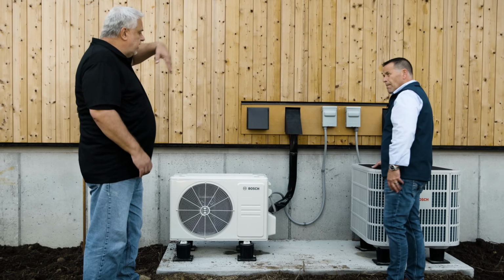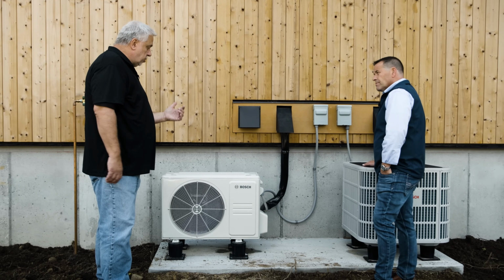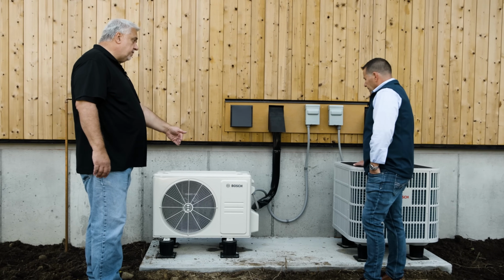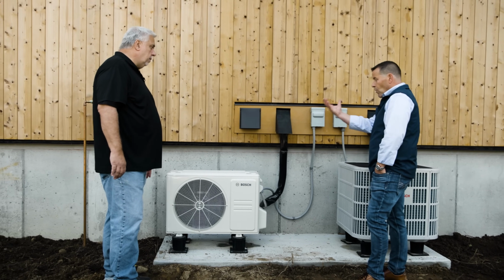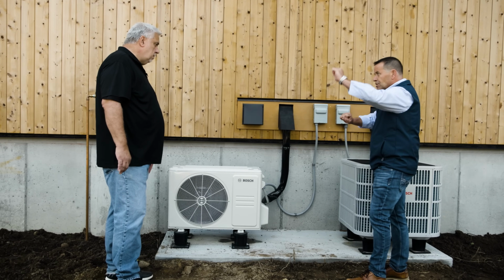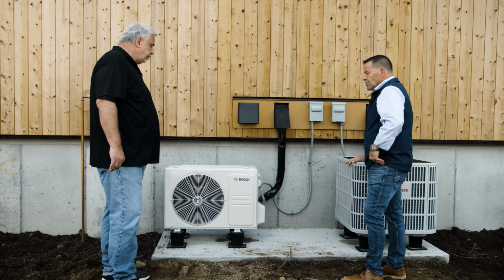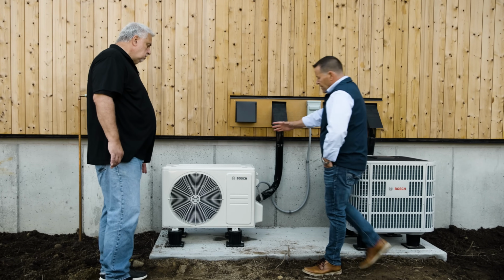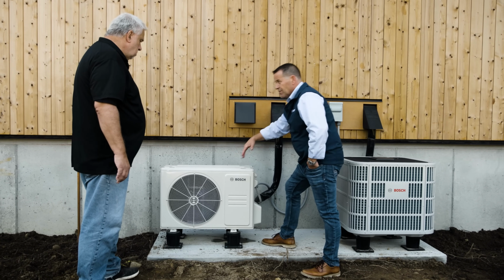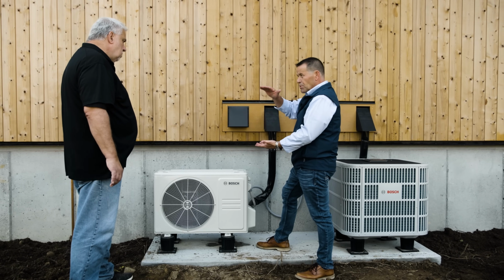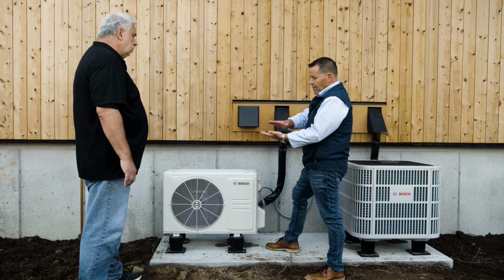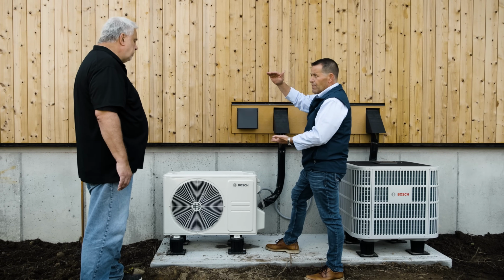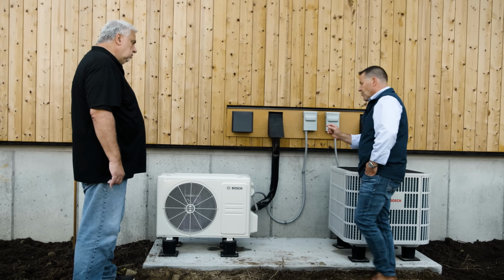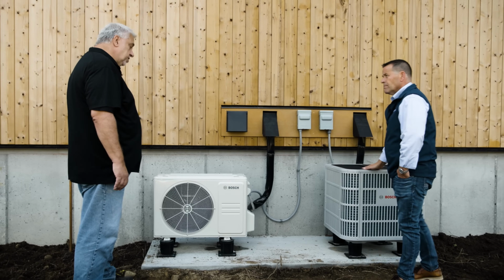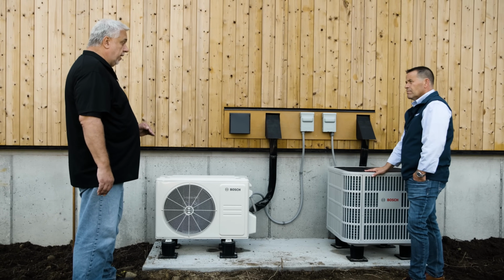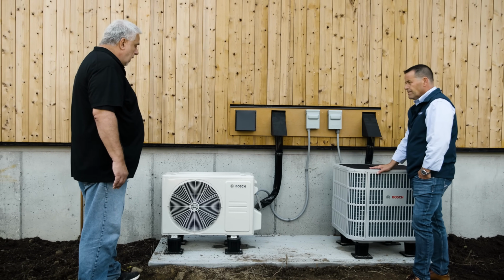If I went that route with 5 systems, do I have the ability to prioritize those 5? No, because they all run together with one compressor, feeding each zone what it requires. It's all communicated back because you have an inverter compressor, a variable speed compressor that ranges from 30% all the way up to 100 to 110% capacity, measuring against what it's looking for. So it's only doing the work that's required, not being overworked in any way.